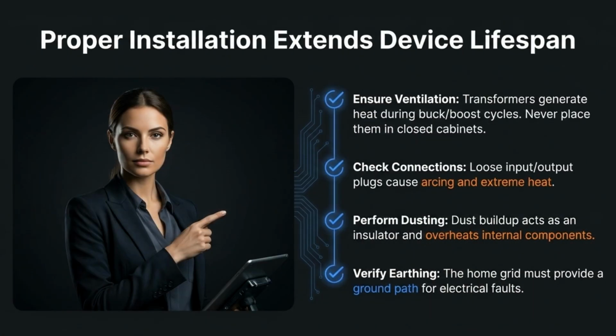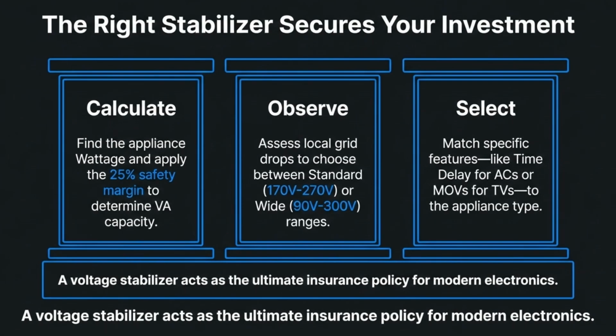Proper installation extends the device lifespan. Ensure ventilation. Check connections to prevent arcing. Perform dusting to avoid overheating, and verify earthing for proper fault protection. To secure your investment, calculate capacity by applying a 25% safety margin, observe your local grid to choose the correct working range, and select features like time delay or MOVs to match your appliance.